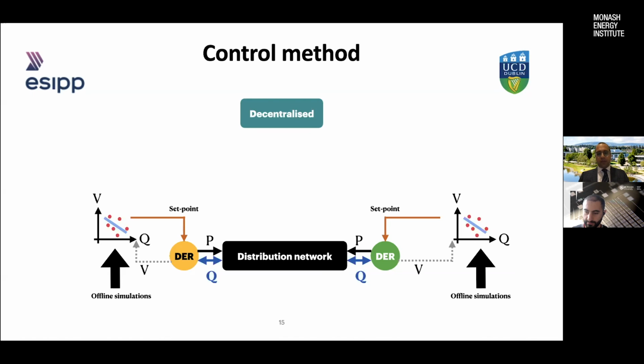First, we avoided some complicated communication system requirements. Then we realized that by implementing these techniques, we reduced active losses in the system—if I remember correctly, something between 5 to 10% in that specific network. You might say this isn't a solid number for every distribution network, which is correct, but the average saving was between 5 to 10% in terms of active losses in the grid. The bigger the network, the more those savings might increase.